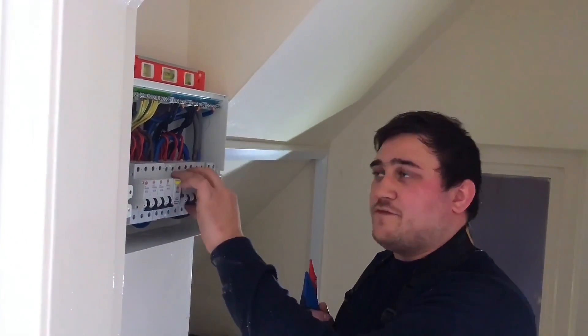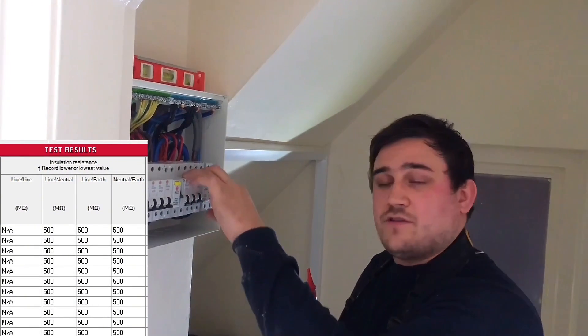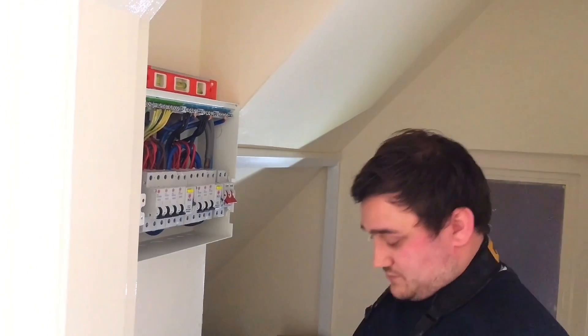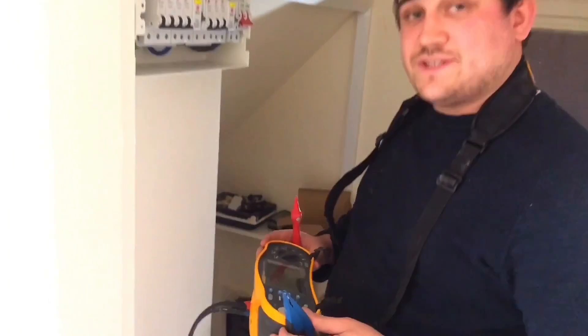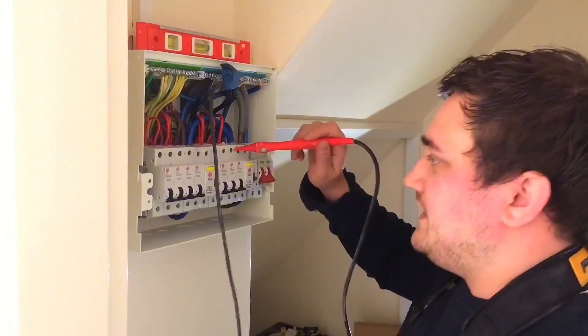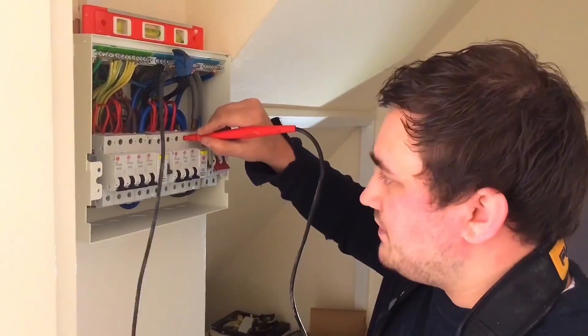I'm going to go between line and neutral first, as the NICEIC domestic and solar paperwork allows me to do so. The BS7671 actually only allows you to do between live conductors and earth, where we would have to link them together — we don't have to in this case. So I've set my tester to 500 volts DC. I'm going to probe onto the neutral bar for this side of the RCD, and then on the top of the breakers.